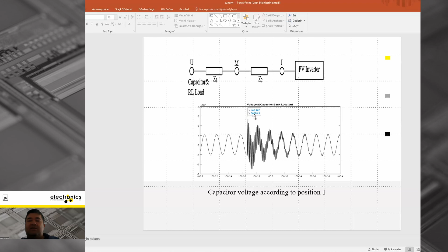In the second scenario or position, we change the place of the capacitor and RL load to the high side, which is near the PV inverter site. And we see here our voltage of the capacitor is 28,000 volts. The voltage change on the capacitance after the reclose depends on the position of the capacitor and RL load. The transient peak voltage on the power factor capacitor is 28,000 volts. Accordingly, we wrote the conclusion.